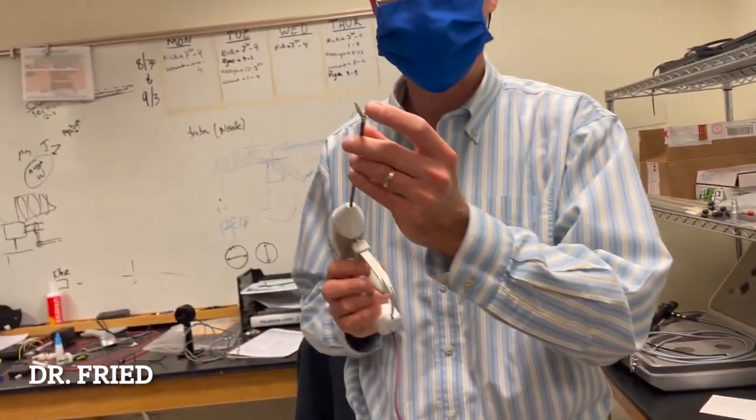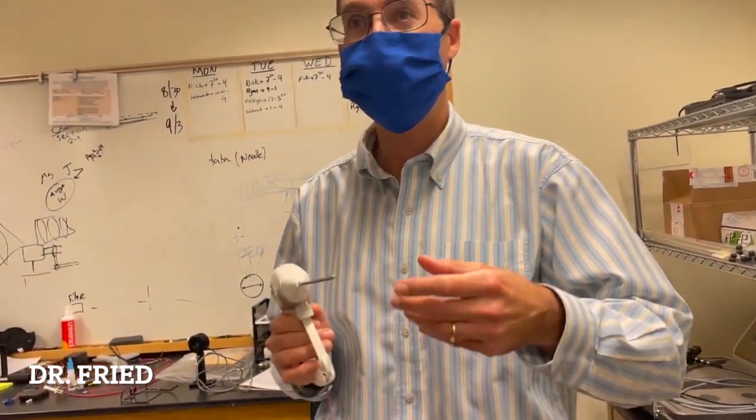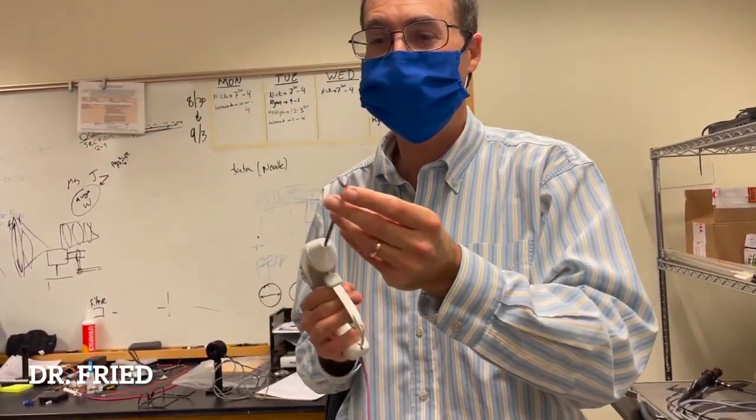Also, the jaws of the instruments here get really really hot, and so the surgeon has to wait a long time for them to cool down before they can do the next seal and cut. And so it's a very inefficient slow procedure.